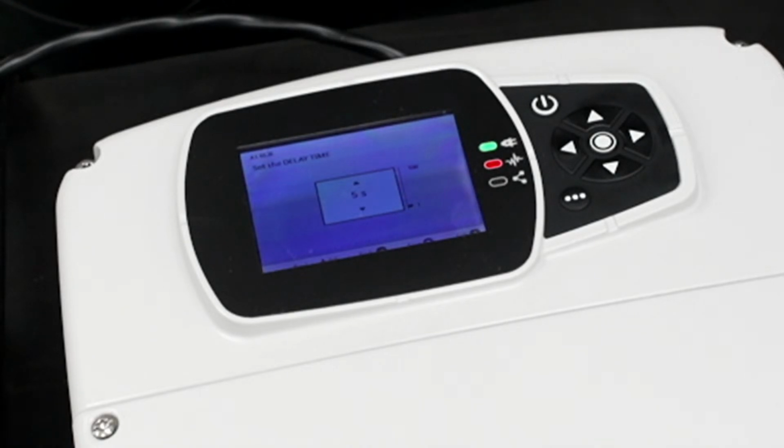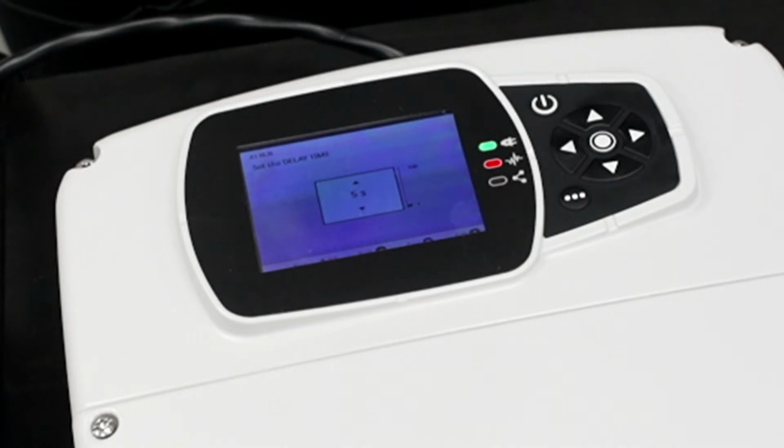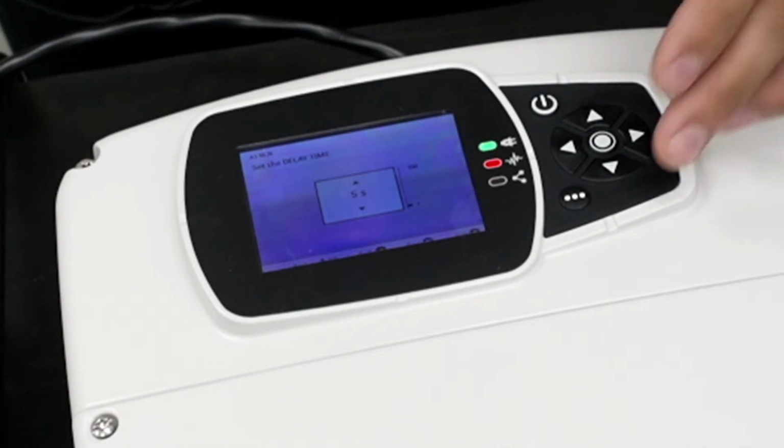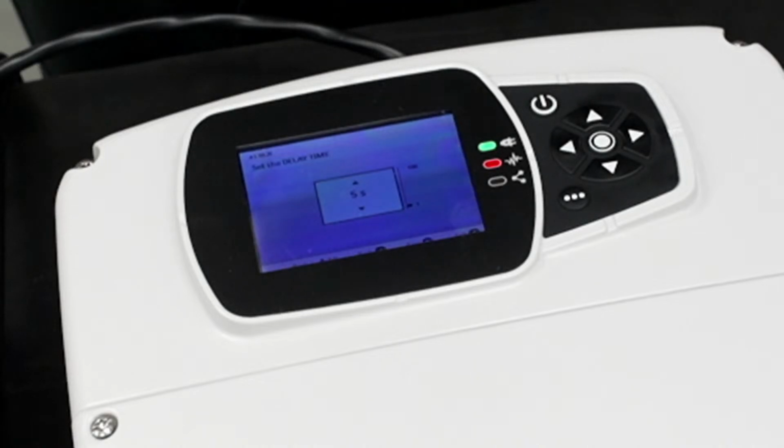So if you don't have this on and that pipe breaks, it's just going to continue to pump at full speed, try to get up to your set point and never shut off. So if there happens to be a broken pipe, you give this kind of prove out thing and it's saying something's wrong, let me shut down so I don't flood a facility or something of that nature.